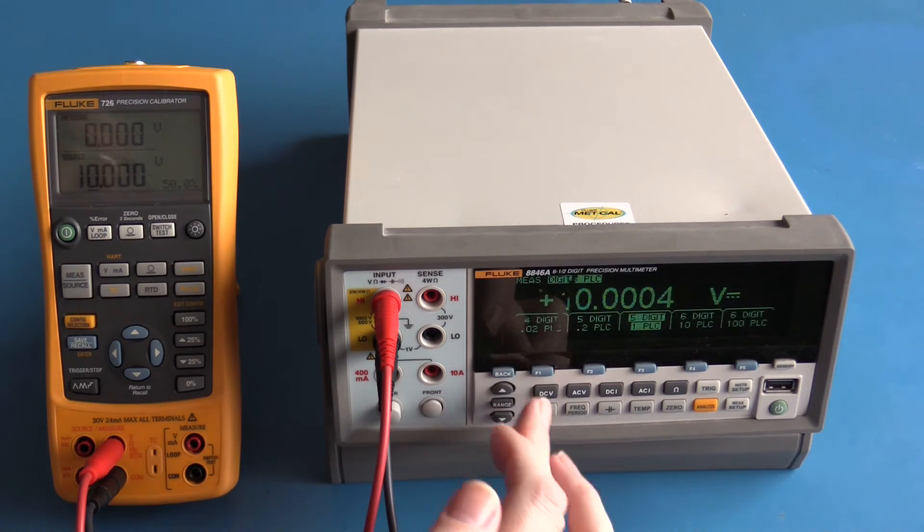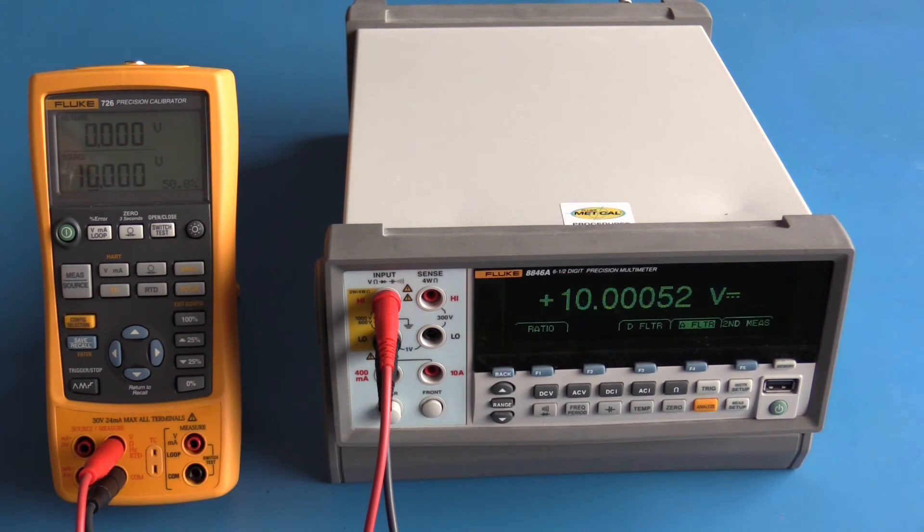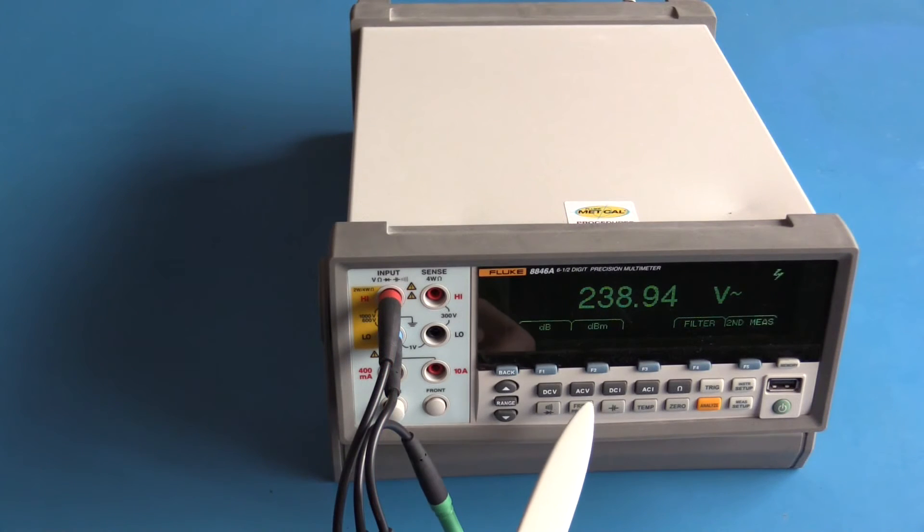I'm now using AC volts. The meter is set up in its medium resolution mode. We have a little warning on the display that a voltage greater than 30 volts is present. We're measuring approximately 240 volts. I'm going to use the second measurement function to look at the line frequency: 240 volts at approximately 50 hertz.